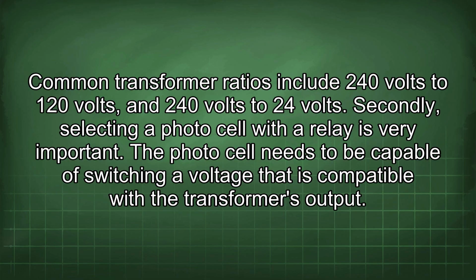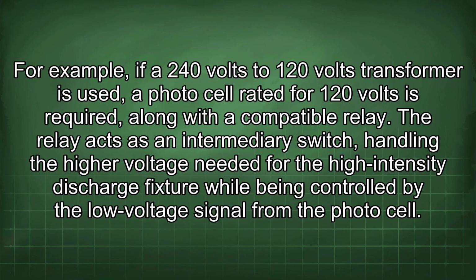Secondly, selecting a photocell with a relay is very important. The photocell needs to be capable of switching a voltage that is compatible with the transformer's output. For example, if a 240 volts to 120 volts transformer is used, a photocell rated for 120 volts is required, along with a compatible relay. The relay acts as an intermediary switch, handling the higher voltage needed for the high-intensity discharge fixture while being controlled by the low-voltage signal from the photocell.